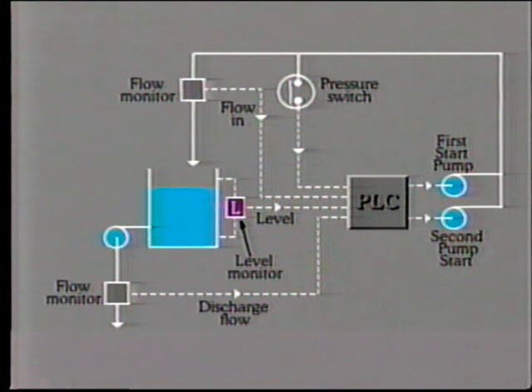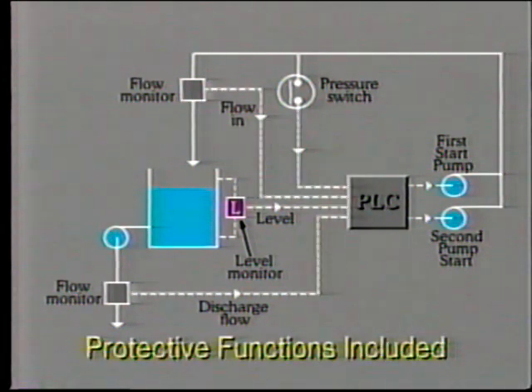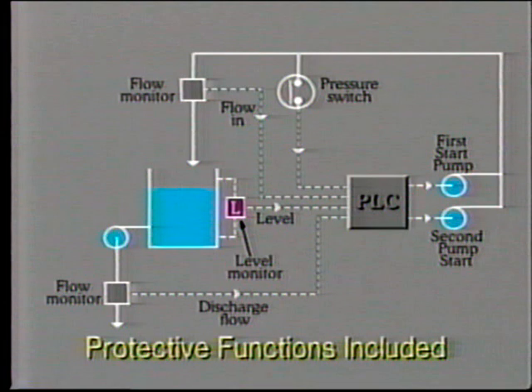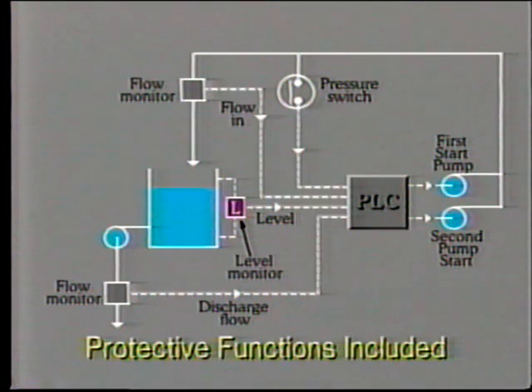When looking at PLCs, we must remember that we are not talking about protection relays. Discrete protective relays are still installed to protect equipment. The PLC looks at the overall control loop and takes action to satisfy a number of different conditions. However, some protective functions are often included within the control logic.